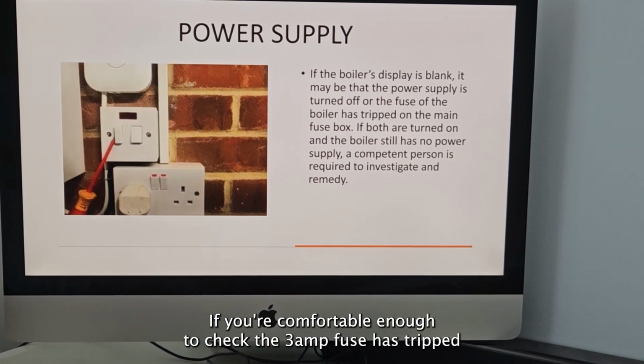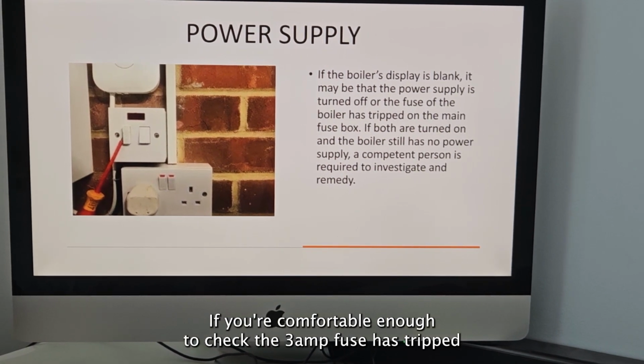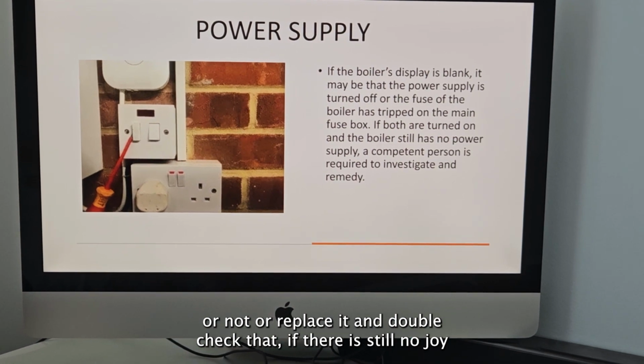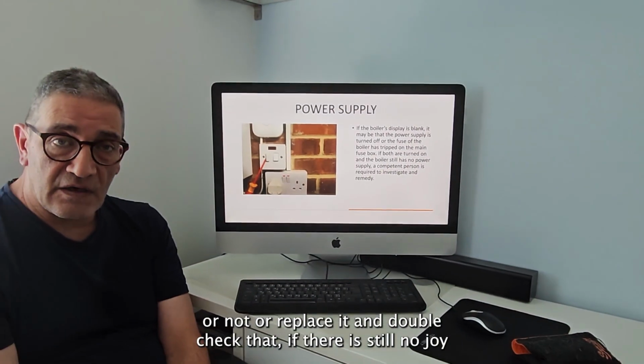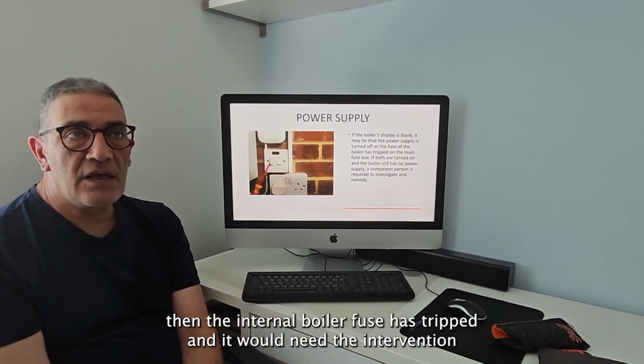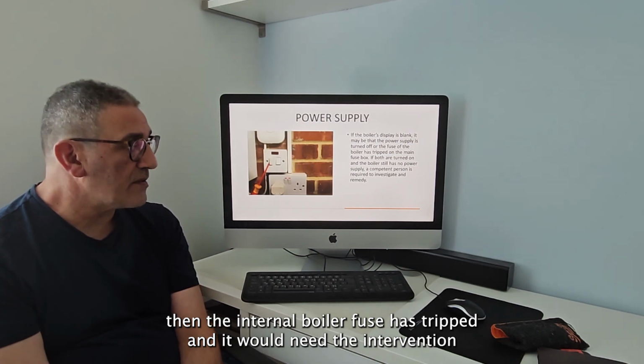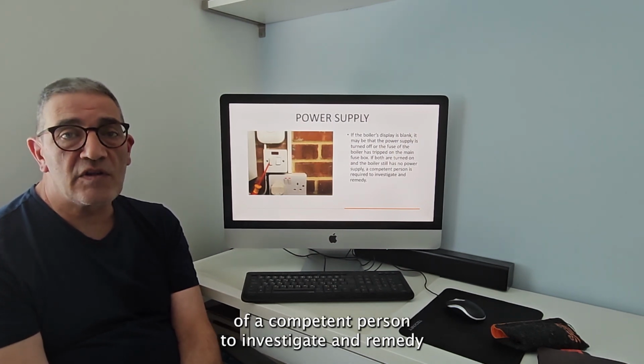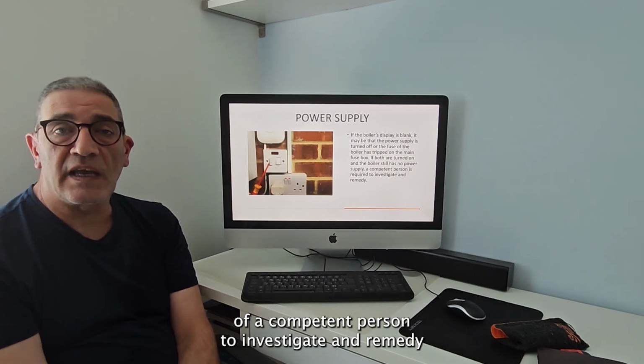If you're comfortable enough to check whether the 3-amp fuse has tripped or not, or replace it and double check that. If there is still no joy, then the internal boiler fuse has tripped and it would need the intervention of a competent person to investigate and remedy.